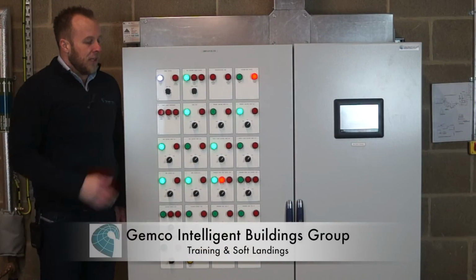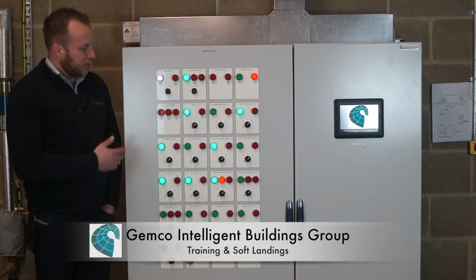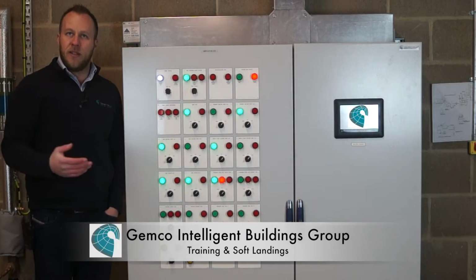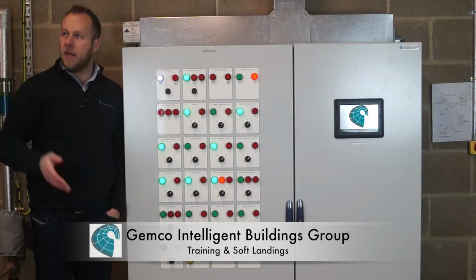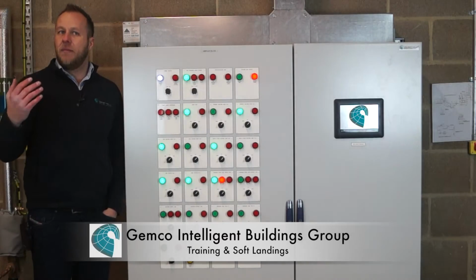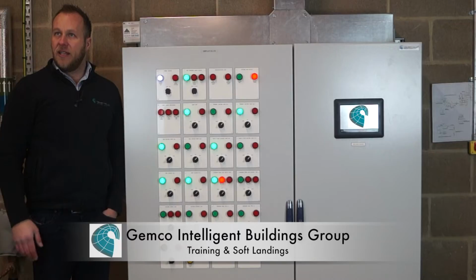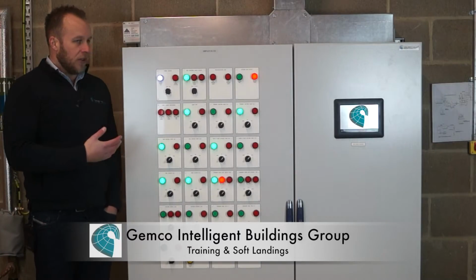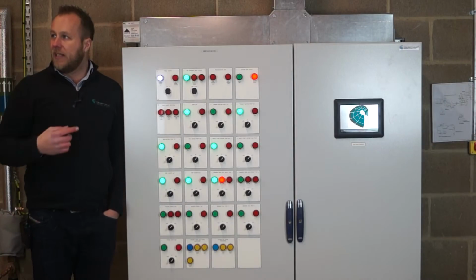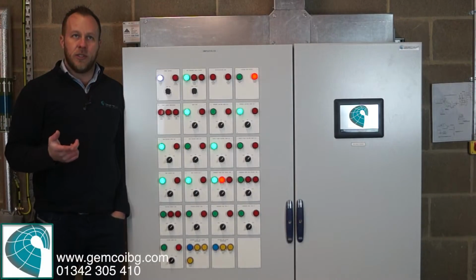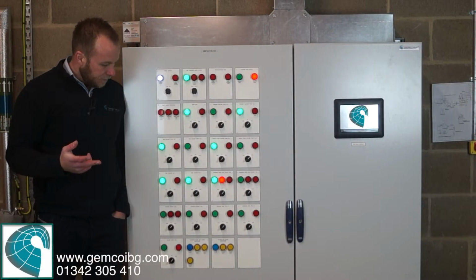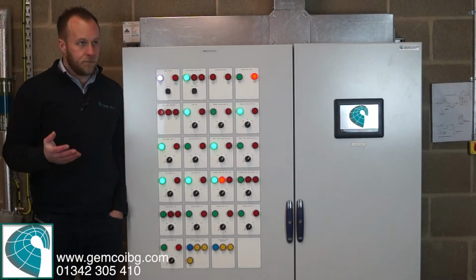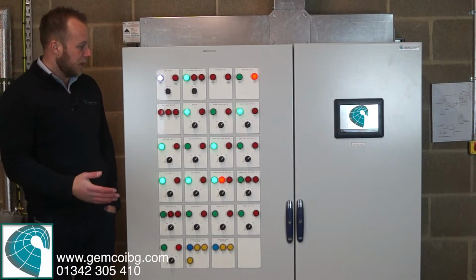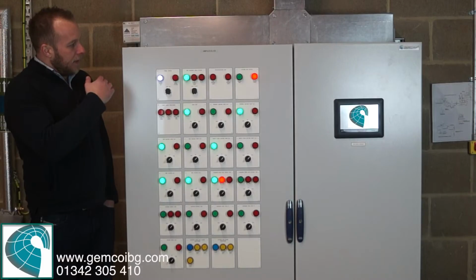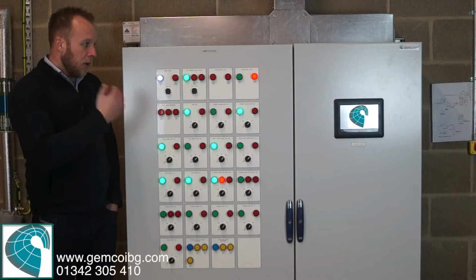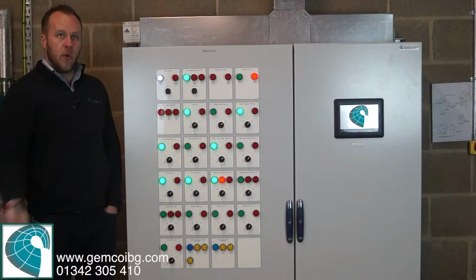All right, so this is the control panel. This feeds all of your main plant. So it feeds your hot water heaters, your pumps that do your heating, and the GHP boiler outside. It's also responsible for feeding your ventilation. So you've got various fans in the building, one in your changing room, your drying room, and you've got Honours Hall fan as well, and the kitchen. So there's some ventilation fed from here as well. And this control panel will monitor and control all of that plant.